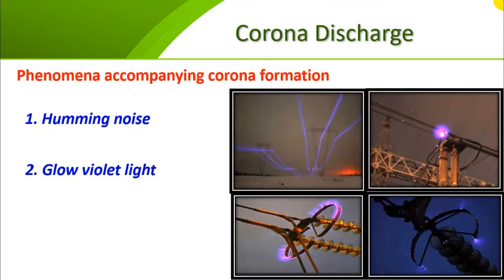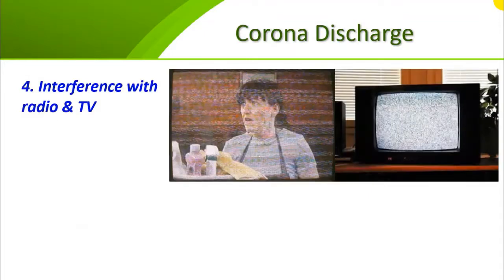Also, when corona occurs, power losses take place over the entire length of the transmission line. These losses, of course, decrease the efficiency of the line. Another thing occurs when corona happens: interference with radio and TV. As explained, corona emits humming noise and violet light. They have, of course, high frequency components which can interact with nearby radio receivers or TV. Also, when corona occurs, you may smell the odor of ozone gas.